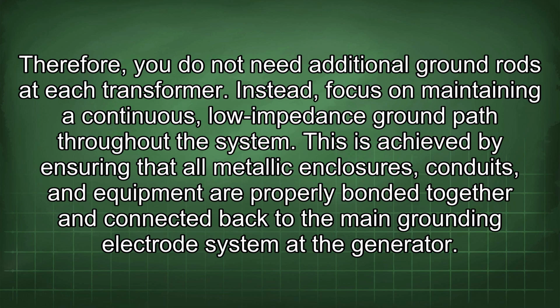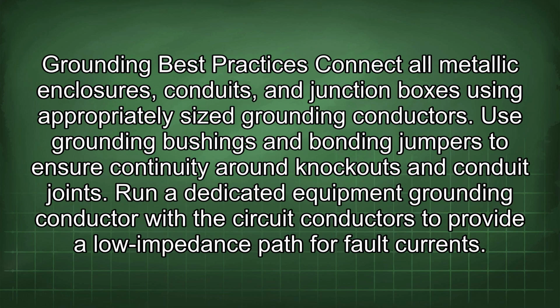Instead, focus on maintaining a continuous, low-impedance ground path throughout the system. This is achieved by ensuring that all metallic enclosures, conduits, and equipment are properly bonded together and connected back to the main grounding electrode system at the generator. Grounding best practices: connect all metallic enclosures, conduits, and junction boxes using appropriately sized grounding conductors. Use grounding bushings and bonding jumpers to ensure continuity around knockouts and conduit joints.